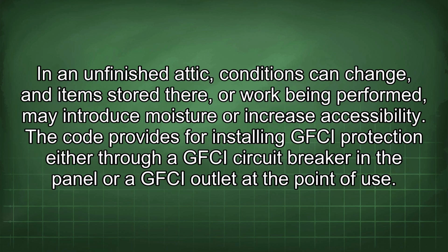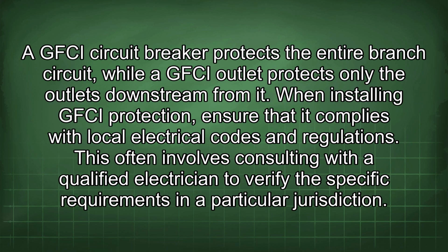In an unfinished attic, conditions can change, and items stored there or work being performed may introduce moisture or increase accessibility. The code provides for installing GFCI protection either through a GFCI circuit breaker in the panel or a GFCI outlet at the point of use. A GFCI circuit breaker protects the entire branch circuit, while a GFCI outlet protects only the outlets downstream from it. When installing GFCI protection, ensure that it complies with local electrical codes and regulations. This often involves consulting with a qualified electrician to verify the specific requirements in a particular jurisdiction.